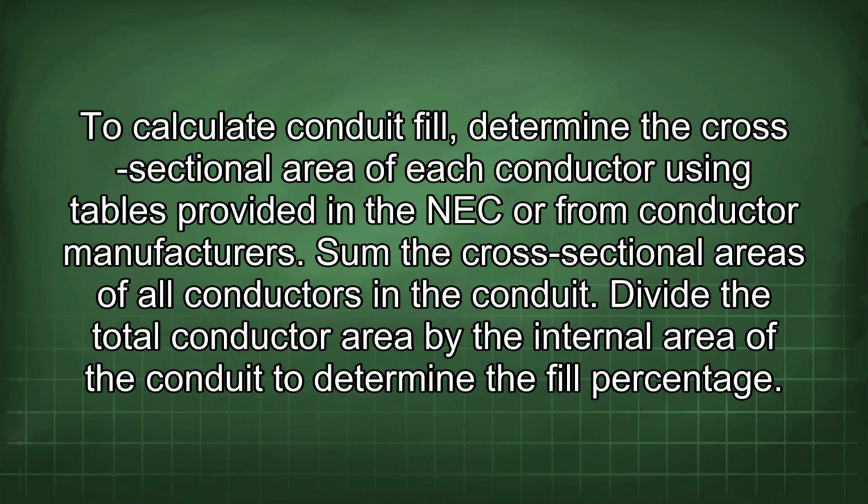To calculate conduit fill, determine the cross-sectional area of each conductor using tables provided in the NEC or from conductor manufacturers. Sum the cross-sectional areas of all conductors in the conduit. Divide the total conductor area by the internal area of the conduit to determine the fill percentage.